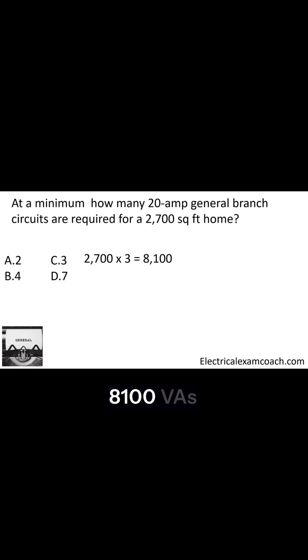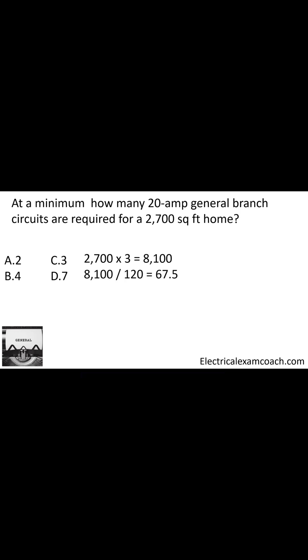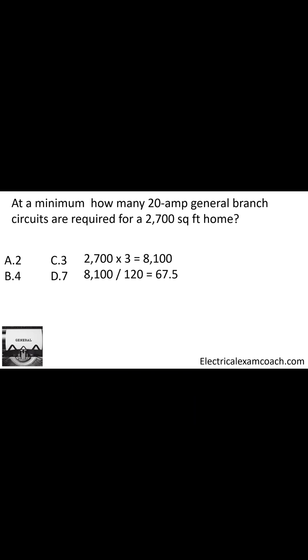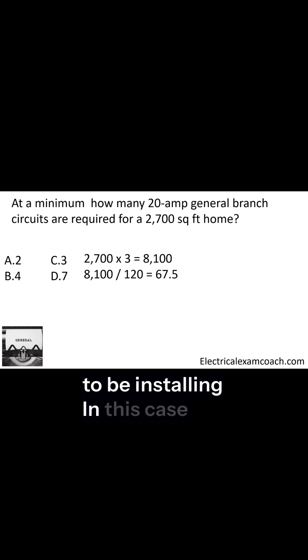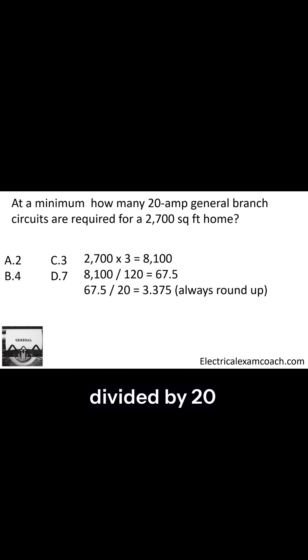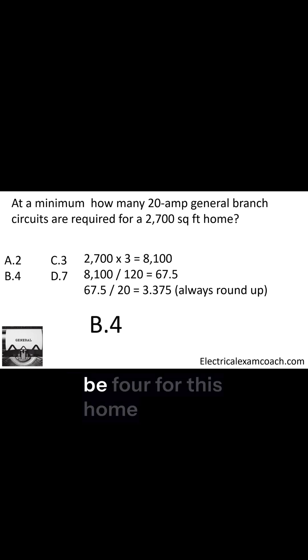That's going to give us 8100 VAs. Now because this is our general lighting, those are all going to be 120 volt circuits. So take that 8100 and divide it by 120 volts, which gives us 67.5 amps. Then we take that and divide it by whatever size branch circuit we're installing — in this case, 20 amp circuits. We take 67.5 divided by 20, which gives us 3.375 circuits. We always round up because you can't have a piece of a circuit, so the correct answer is four for this home.